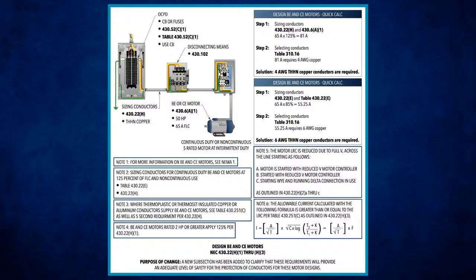Okay, so say I calculate something and I'll use this as an example, and I come up with 58 amps. Now, y'all can follow along with this later and go back and forth, stop it so you can follow along. If I go look at table 310.16, I pick up the 75-degree column, come down, the next size above 58 amps is 65 amps. Okay. Yeah.